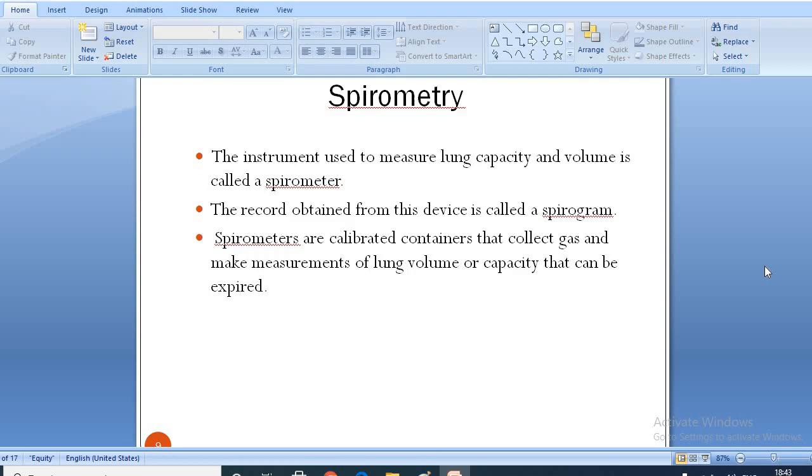The instrument used to measure lung capacity and volume is called a spirometer. Basically, the record obtained from this device is called a spirogram. Spirometers are calibrated containers that collect gas and make measurements of lung volume or capacity that can be expired. By adding a time base, flow dependent qualities can be measured. The addition of gas analyzers makes a spirometer a complete pulmonary function testing laboratory.